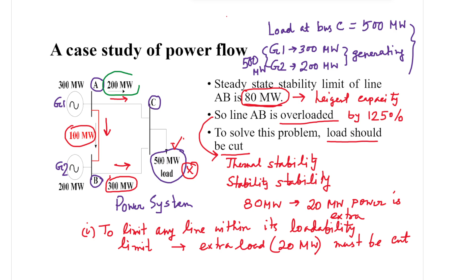Now it can be seen that the power flow drastically changes. Initially line AC was carrying 200 megawatt power without the capacitor, but the moment the capacitor is placed in series, the power transferring ability is enhanced by 30 megawatt. So now it is transferring 230 megawatt of power. So generator G1, which was generating 300 megawatt of power, now 230 megawatt is carried by line AC, and the rest 70 megawatt is carried by line AB.